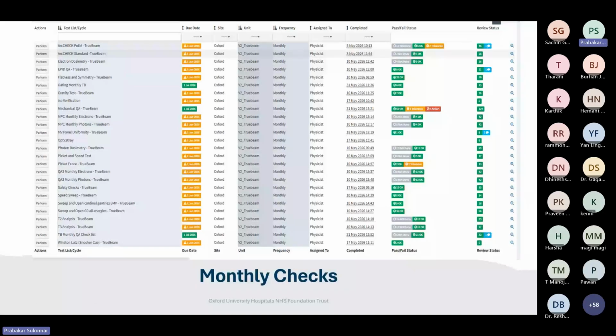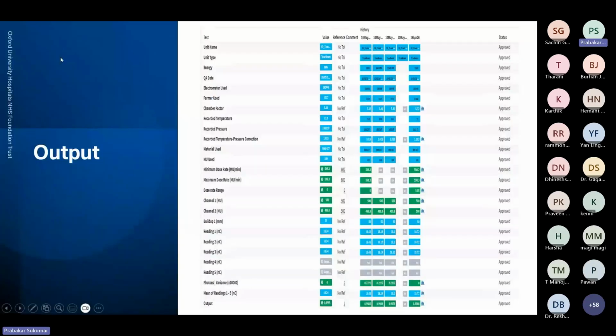And coming back to the outputs, we created a test, each one is a different test. You have to choose your unit and what type of unit it is, whether TrueBeam or Halcyon, whatever energy you are choosing. You have to enter the energy, and then you have to enter the QA date that you are performing. Each one is a test, and then there is the whole collective test list.